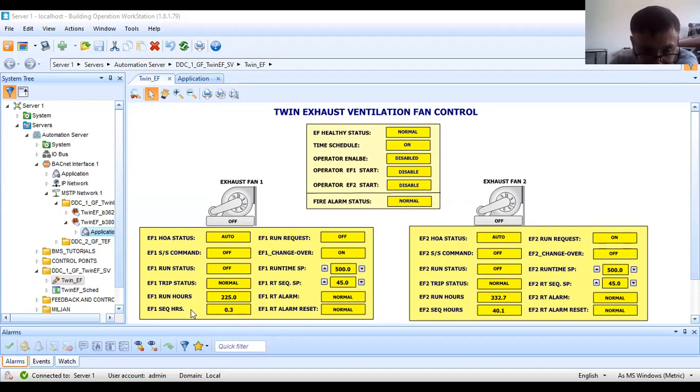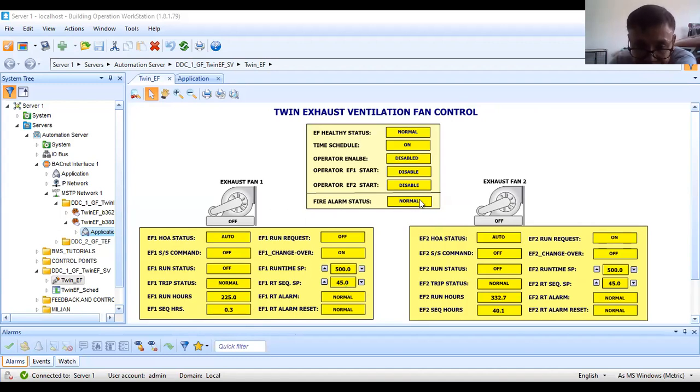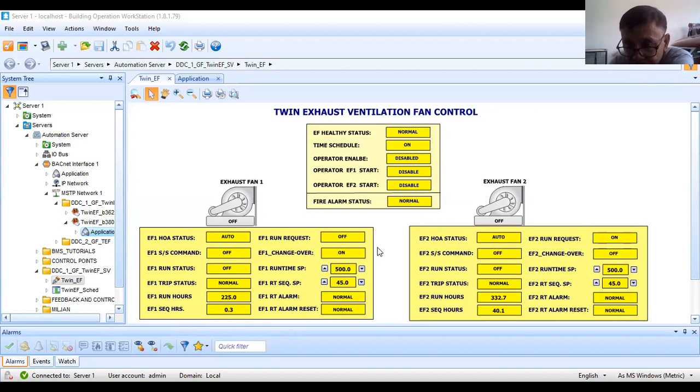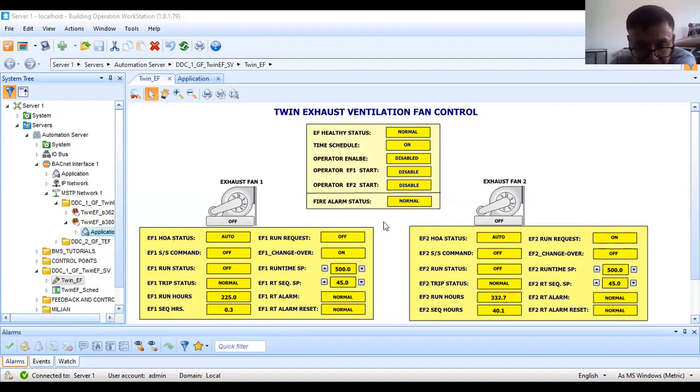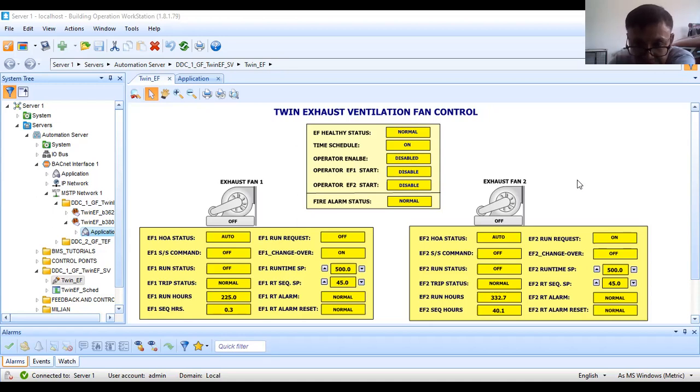For the sequencing, this is to provide equal wear and tear. By default, 168 hours. So every week, these two fans will change over. I have here the run request. Since I've been running this for quite some time, as you can see, there are already some values. I think I already explained this, and we will try to simulate the operation.